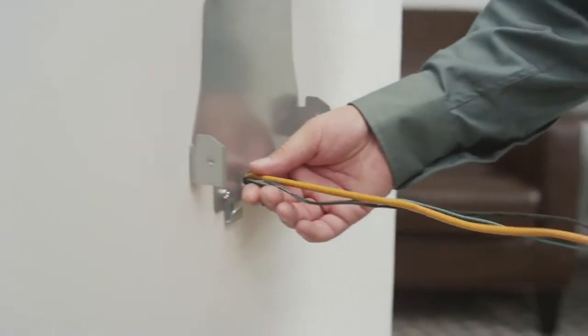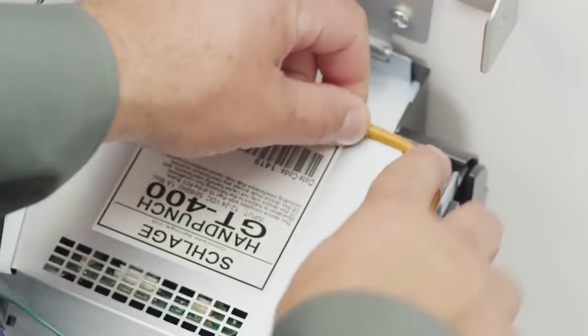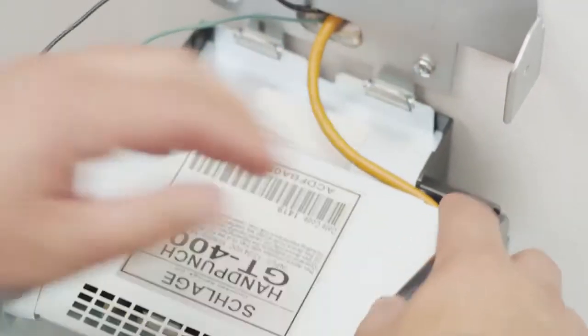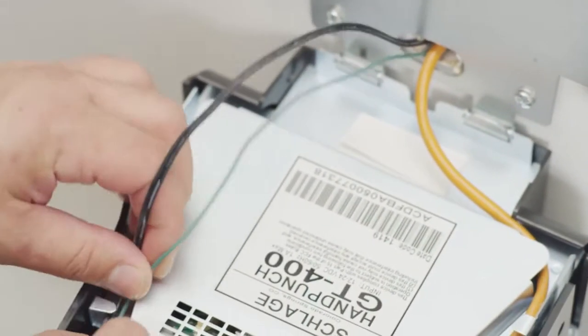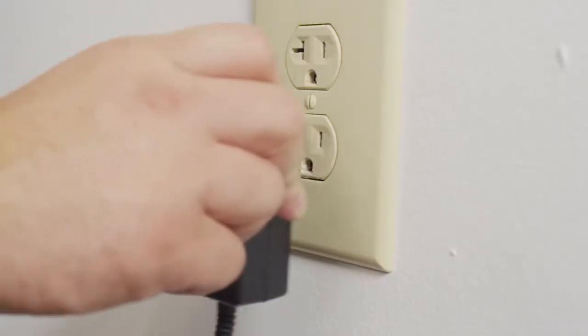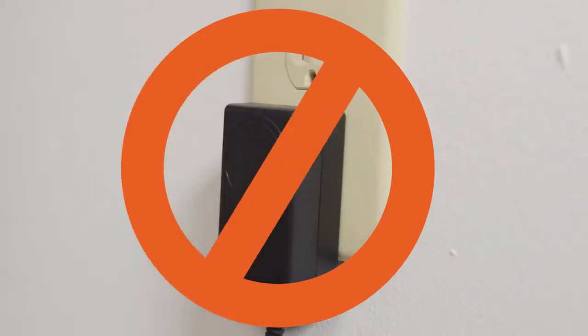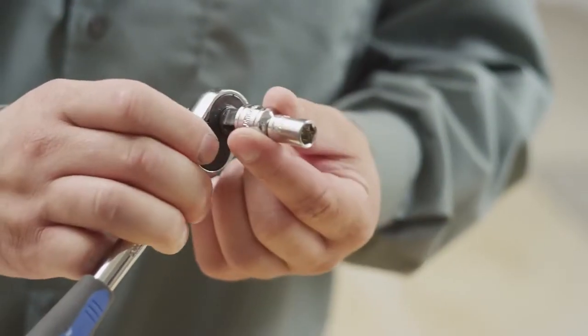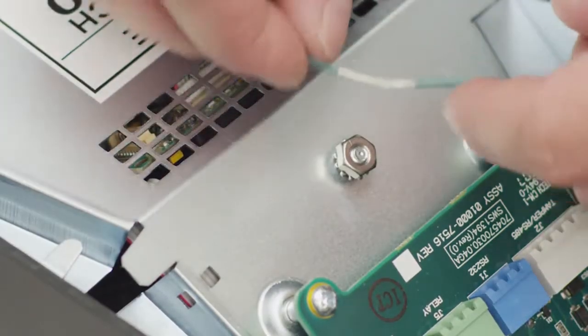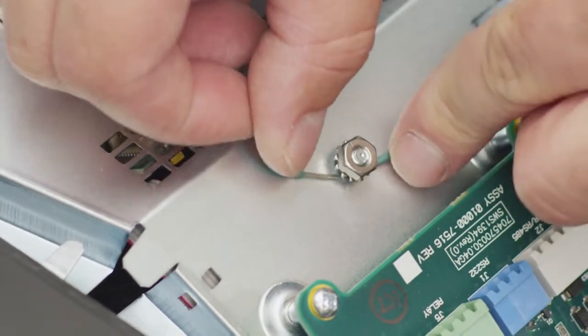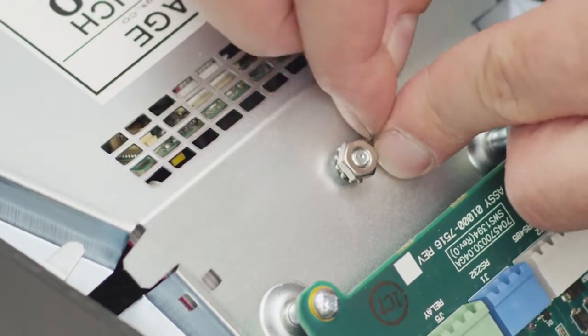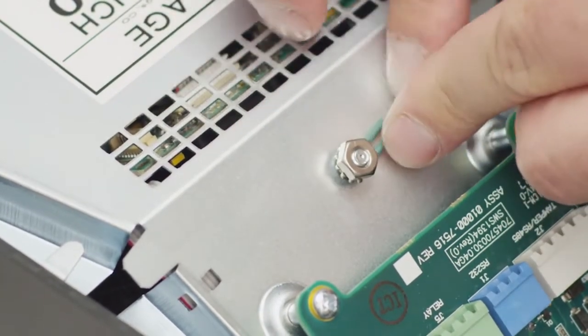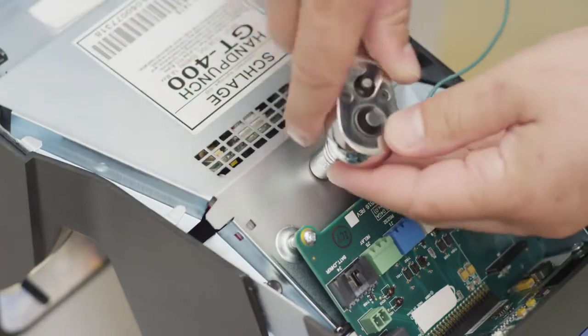Run wiring using the method previously chosen. Tuck wires under the tabs on the terminal to minimize risk of pinching. Do not apply power until you are ready to configure the terminal. Connect the earth ground. The earth ground connection is made to the ground pin on the back plate with an 8/32-inch nut.